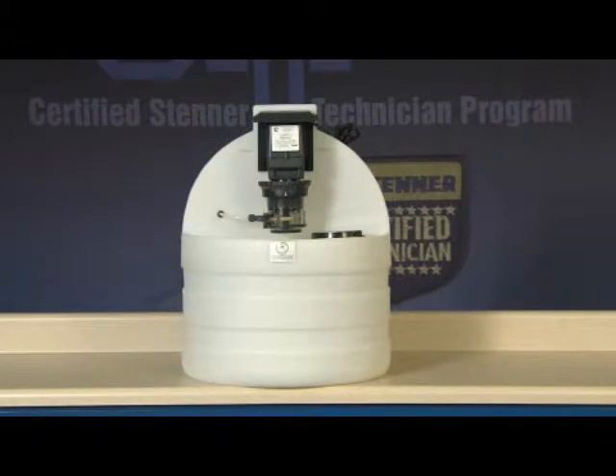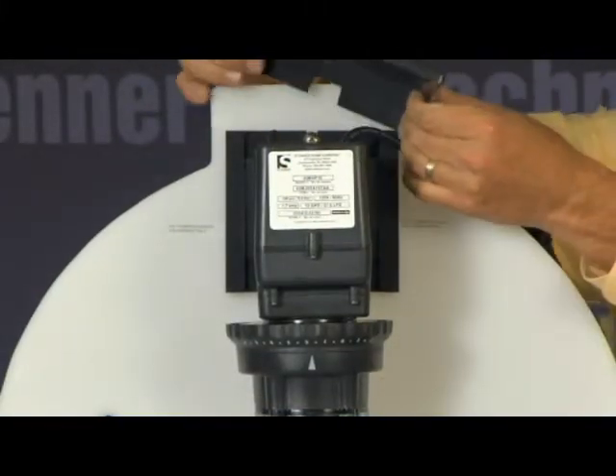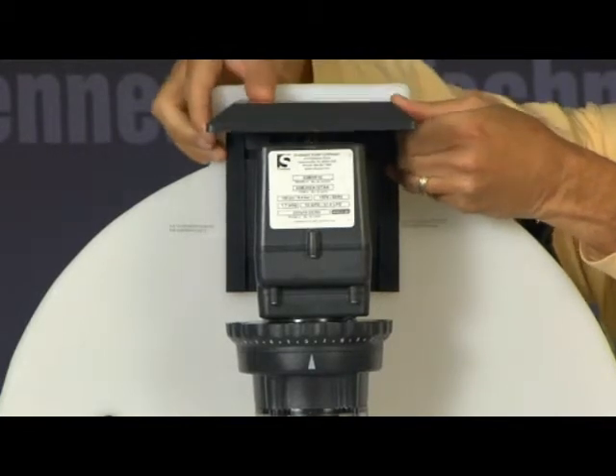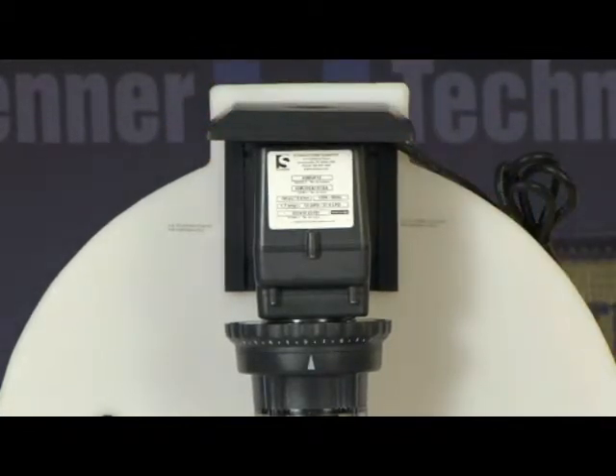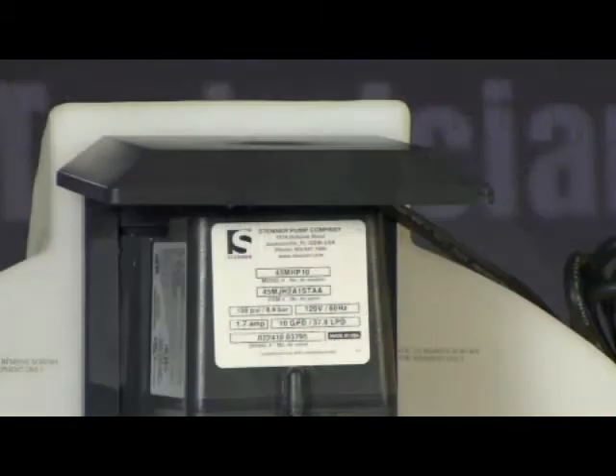Mount the pump vertically with the pump head in a downward position and never with the pump head pointing up, to keep solutions from collecting in the tube housing or seeping into the feed rate control and motor, which can seize the moving parts. With a vertical mount, the rain roof slides onto the mounting bracket to help protect the ventilated motor from water intrusion that can cause motor damage. The rain roof is recommended for outdoor environments and installation subject to washdowns.